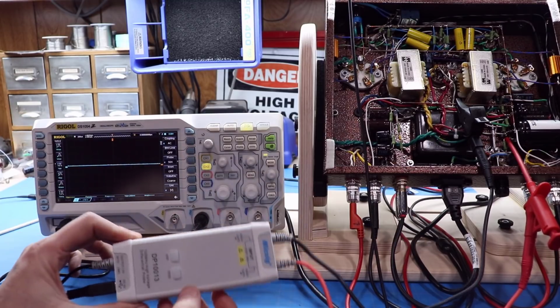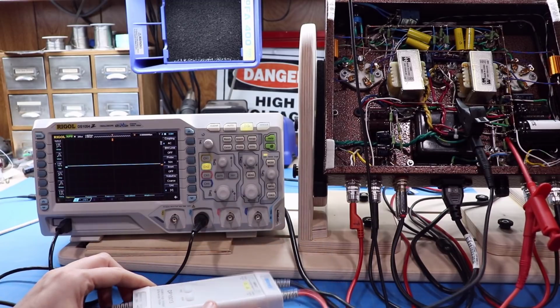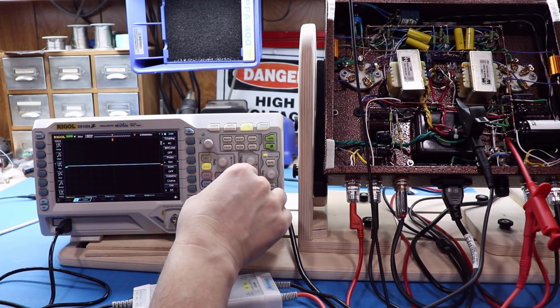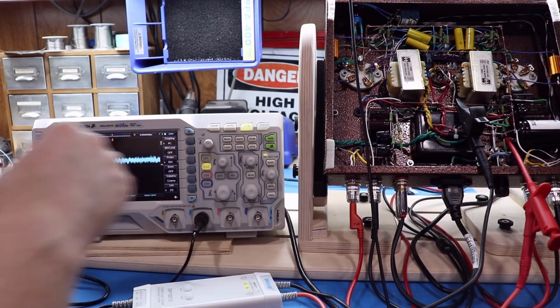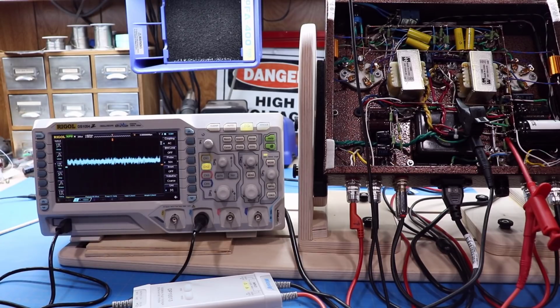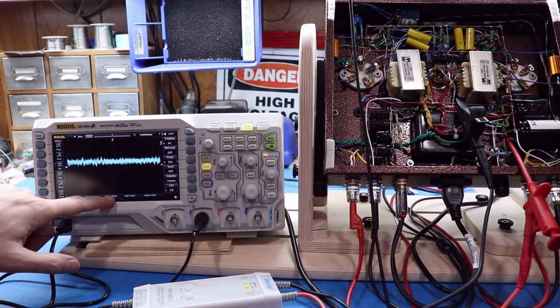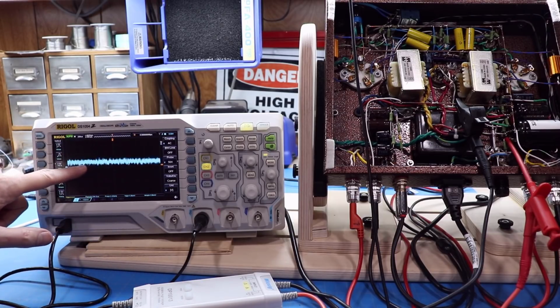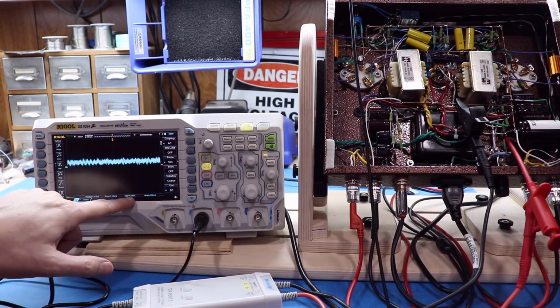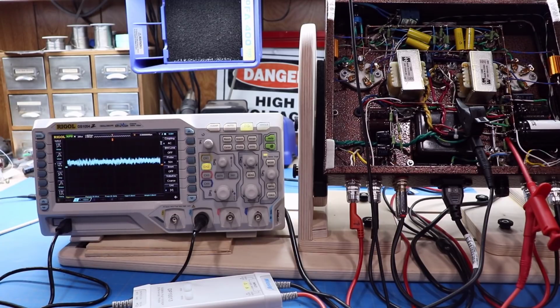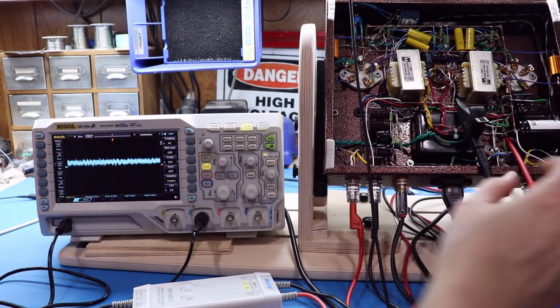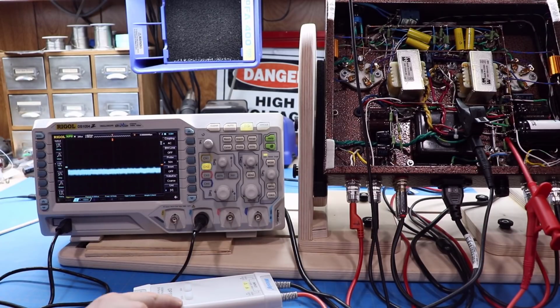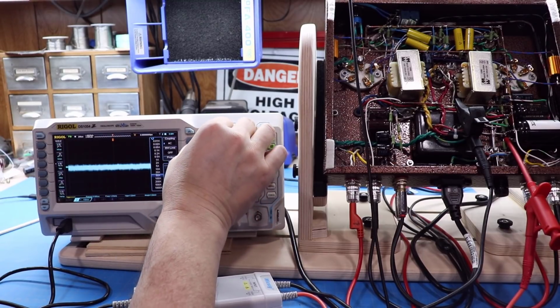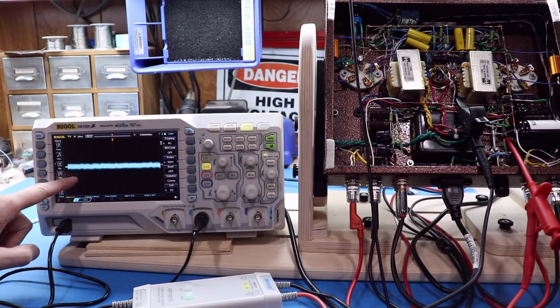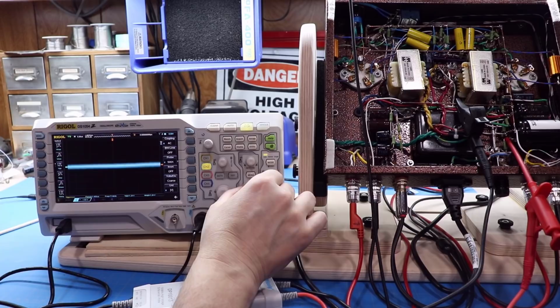But I'm AC coupled, and guess what? I've got a differential probe here, and I'm telling it I've got times 50 here. So we should be able to play around and start to see a teeny little bit of noise. And if you'll notice, the noise here is bouncing around way up around 20 kilohertz. So I've got a little bit of high frequency on my B plus there, and way down around 100 or 120 millivolts down here. So these things do come in handy and can help you out in what you're measuring. And what it's telling me is I might want to switch over to 500 here, and then I would change this probe over and drop it down to the 500 point here, and you can start to see some of this noise a little bit, maybe even start to diagnose a little bit of it.